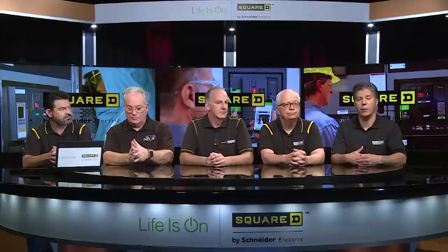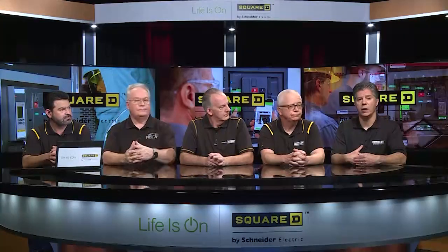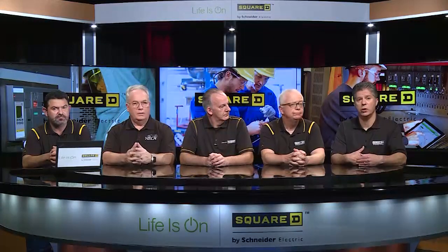Switchboards and switchgear, motor control centers, large products such as those lend themselves to reconditioning, and as you go into those sections of the NEC, you will see the allowances for reconditioning. Transfer switches, whether we're talking about Article 700, 701, 702, or 708, it's clearly stated that transfer switches are items that cannot be reconditioned.